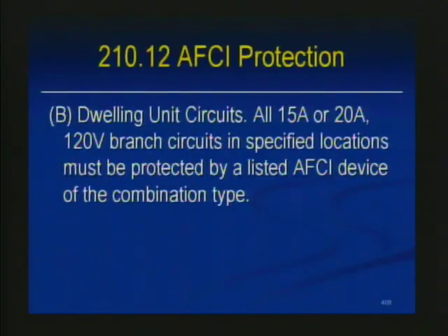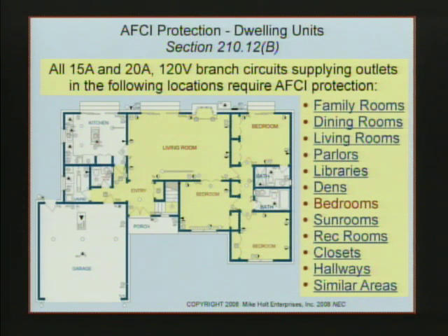All right, let's go now getting into the rule itself. Now we understand more than we probably want to know about AFCIs. All 15 and 20 ampere 120 volt circuits in specific locations must be protected by a listed AFCI device of the combination type. Combination was a series and a parallel. Where do you need AFCI protection? Well, big change in the 2008 code. Family rooms, dining rooms, living rooms, parlors, libraries, dens. It originally was only bedrooms, sunrooms, rec rooms, closets, hallways, similar areas. We're talking a huge expansion.